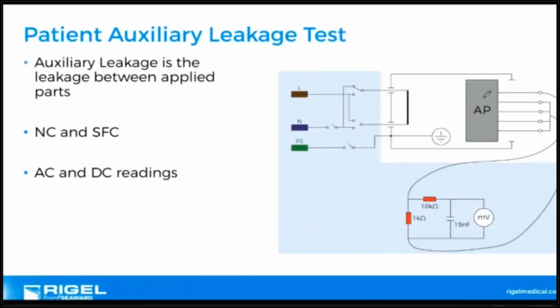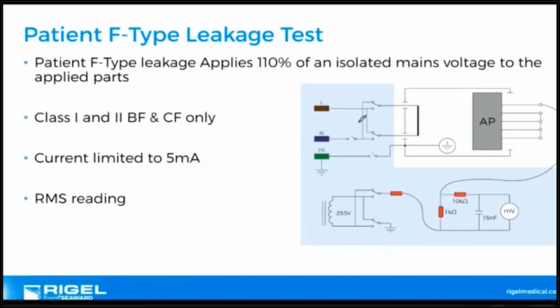Patient auxiliary, what we're doing here is we've got our functional current, any stray capacitance, etc. You get the picture. What we're doing now is measuring any current that might flow between patient ports. That's what auxiliary leakage does, both AC and DC. F-type leakage is where we put mains on the applied ports. So powering the device, that's your functional current. But what we're doing internally, bearing in mind this powder blue here is internal to the device, or whatever electrical safety analyzer you're using, is we have an internal transformer that's isolated, with a single fault condition where we can reverse live and neutral.